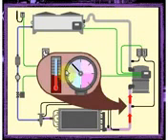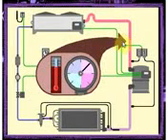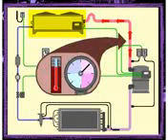Under normal operating conditions, the compressor runs as long as the thermostat has not reached the desired room temperature. The gaseous refrigerant which is drawn in from the evaporator is compressed to a high pressure. The refrigerant temperature then rises instantly with the increase in pressure, and the refrigerant flows towards the condenser. In order to try to adapt to the variable flow of the refrigerant arriving at the compressor, some systems use multiple compressors. As the flow of refrigerant increases, the suction pressure increases, which in turn allows a larger number of compressors to start up.